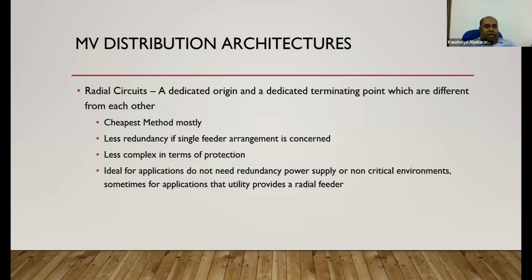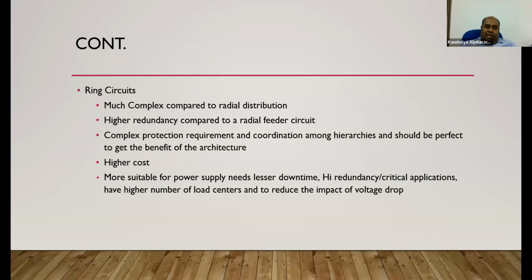But even though you have a single feeder from the utility, you still can have a ring circuit at your end, at the user's end. But if there are not many load centers for MV distribution, that may not be necessary, unless you need internal redundancy. Ring circuits are, of course, much more complex compared to a radial distribution. In a radial distribution, your utility's medium voltage primary panel is there, and you get a single feed from there to your secondary distribution system, and from that secondary distribution system you have a dedicated cable ending at your load center.